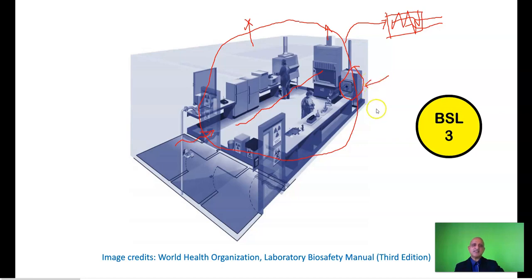This will require specific engineering requirements, as the autoclave has to be designed so as to work within this facility, and this may involve an additional heat load on the facility. So that's where engineers come in, and they have to focus on their HVAC, or heating, ventilation, air conditioning and cooling systems. And everything else is basically as in the BSL2 with the disposal containers. However, you will note something at the entrance. This is the vestibule. It can be in the form of an airlock. So ideally, you will have your door with your signage, and for biosecurity reasons, you may have a security protocol in the form of this keypad for signing in or using your thumbprint to access this facility.